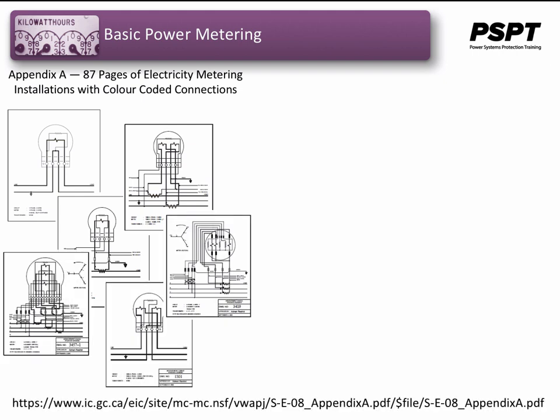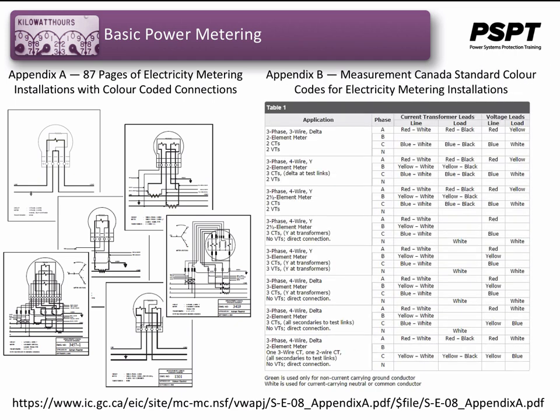The website has two sections: an Appendix A, which is 87 pages of electricity metering installations with color-coded connections, and you can leaf through them. We've gone through several of them here in this chapter. Appendix B is Measurement Canada's standard color codes for electrical metering installations. Now, these color codings don't affect the actual metering themselves, but what they do is they make it easier for those that are maintaining the system to understand how the wires are connected without having to separate out the bundles and have to reconnect or re-bundle them together after maintenance is done.